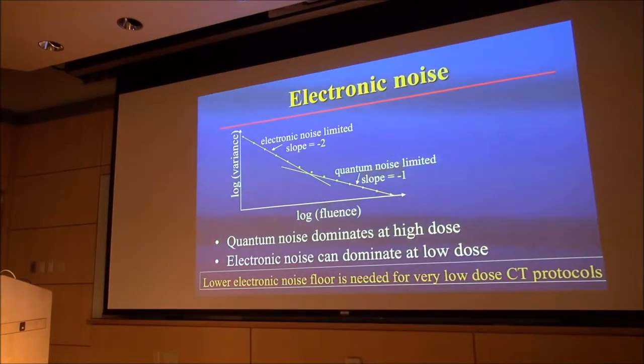There's another problem with our detectors: electronic noise. We expect the variance to go like one over the fluence. If we plot log of variance versus log of fluence, it should have a slope of minus one if it's quantum limited. As the fluence goes down, eventually we run into electronic noise and the slope is minus two. Electronic noise can dominate at low dose. If we want to build systems for very low dose protocols, this will become a limit.